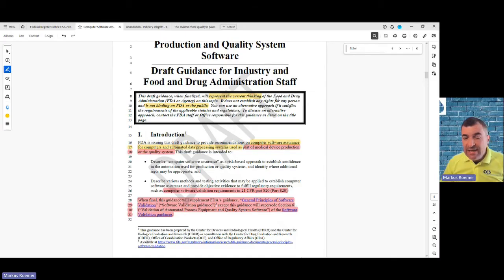Software validation guidelines. And here, people are using the expression software validation. In the pharmaceutical industry, I never talk about software validation. This is maybe also very, very important. There's definitely a don't. Don't talk about software validation when you are in the pharmaceutical industry. I exclusively use the term software validation for a medical device which contains hardware and software as an SaMD or SiMD. There are other requirements in this world, IEC 62304, for example. It is a higher standard than GAMP. GAMP is not applicable to SaMD or SiMD. It is written there in the scope of the document.